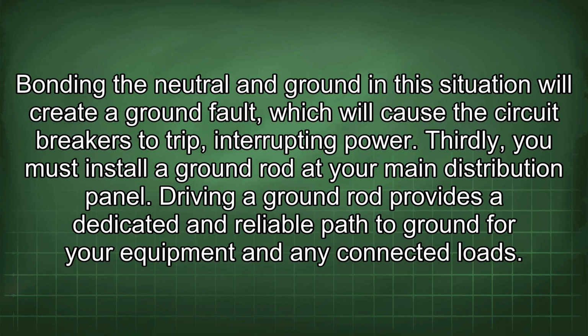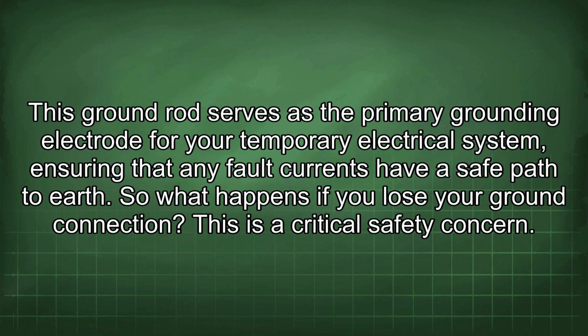Driving a ground rod provides a dedicated and reliable path to ground for your equipment and any connected loads. This ground rod serves as the primary grounding electrode for your temporary electrical system, ensuring that any fault currents have a safe path to earth. So what happens if you lose your ground connection? This is a critical safety concern.